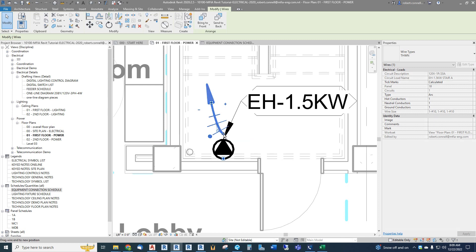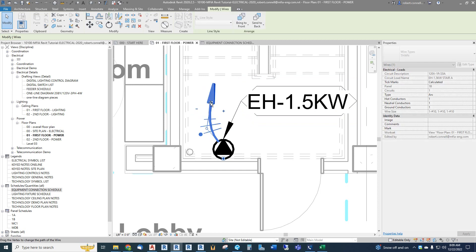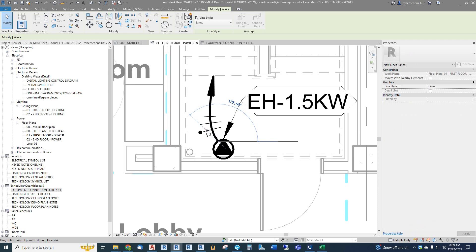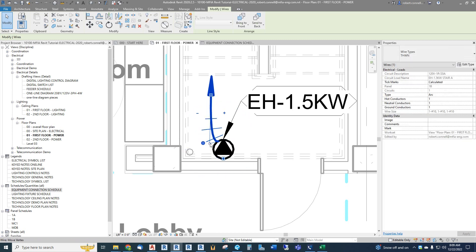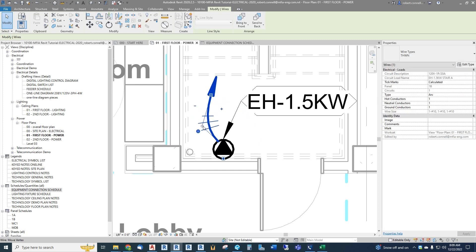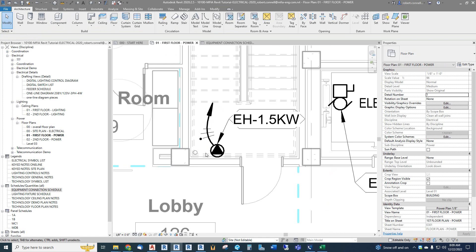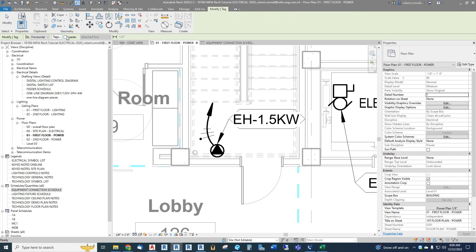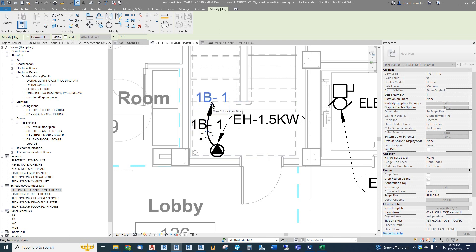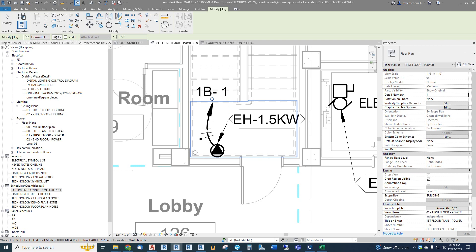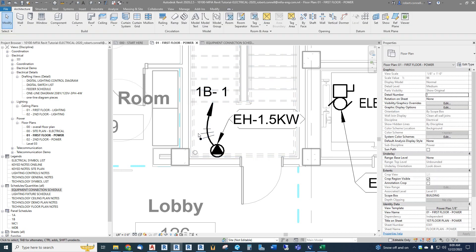The arc has other geometry it's trying to connect to whether it's turned on or off, so we often have to fix the grip. Move the grip down to the actual circle, then graphically adjust it to look how you want. If you pull the grip too far down it spreads out the wires; too close and it makes them look weird, so get it somewhere in the middle to look clean. Then tag it — hit 'Tag by Category' in the quick access toolbar, uncheck the leader, and drag it over the wiring.